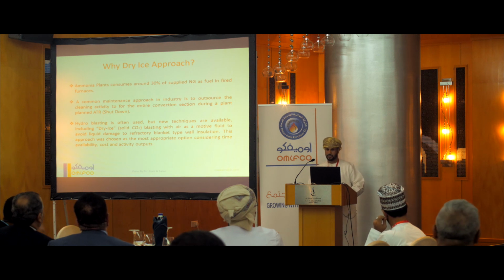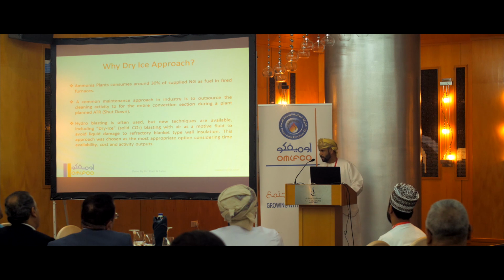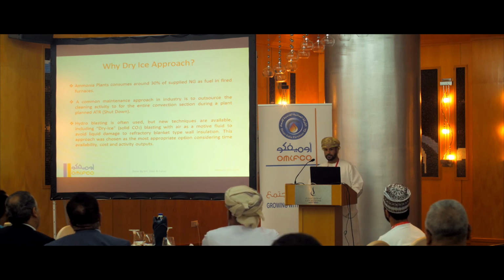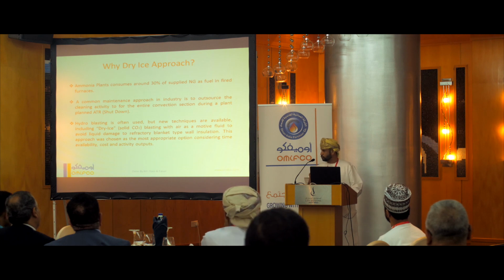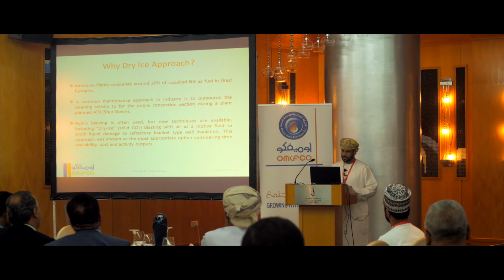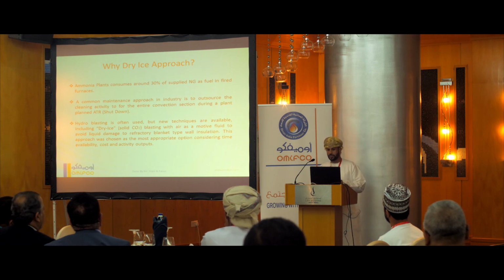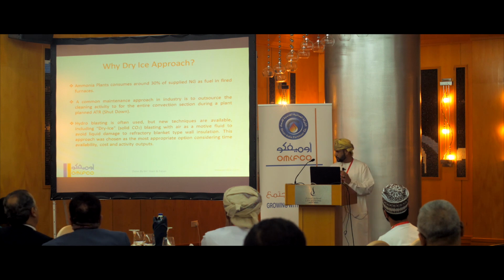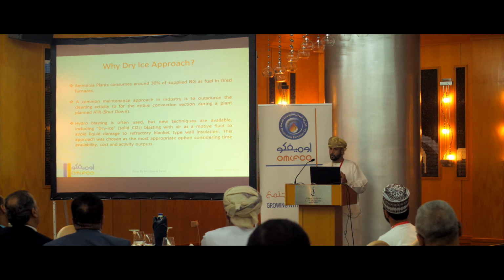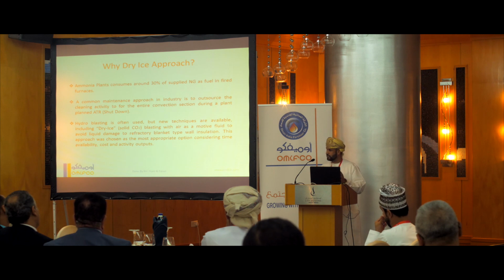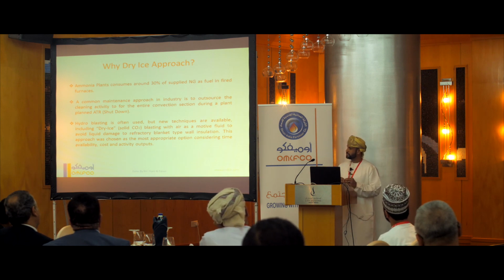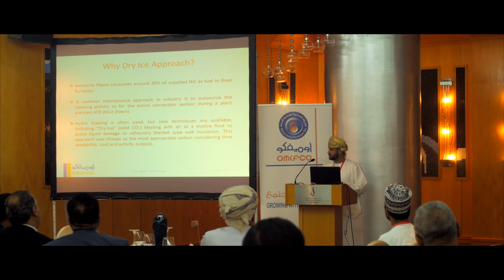Now we'll discuss the main issue of our case study, which is dry ice. Why dry ice? Before, we used sandblasting and even a water jet to remove the deposits in the tubes. But as we know, the ammonia plant is consuming around 30% of the total plant's fuel, the NG, as fuel. So if we can reduce this fuel consumption, we can save energy and get more production. So we use this dry ice cleaning, to get the maximum production or to reduce the fuel gas, so we can get some more production.